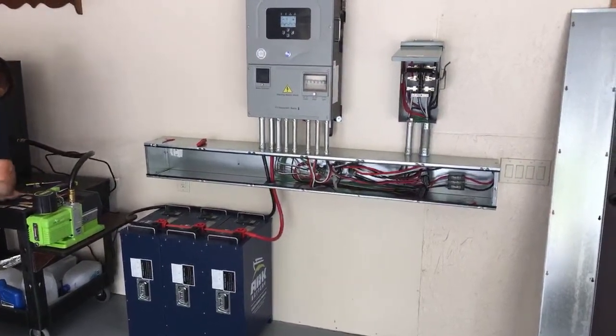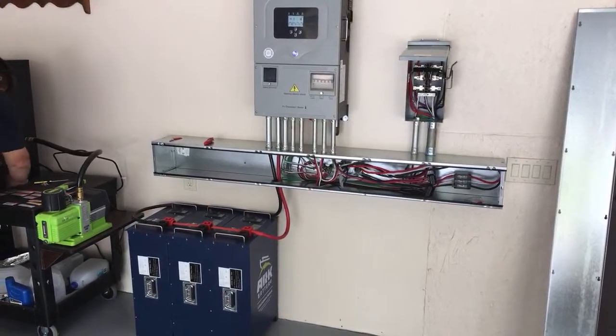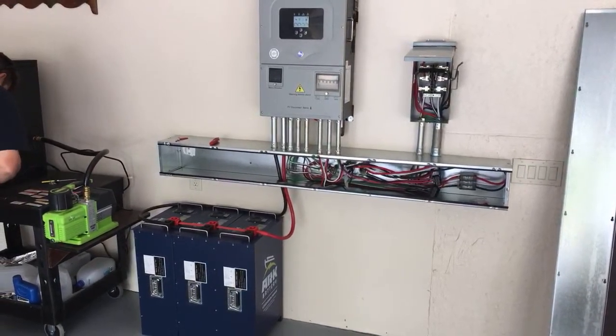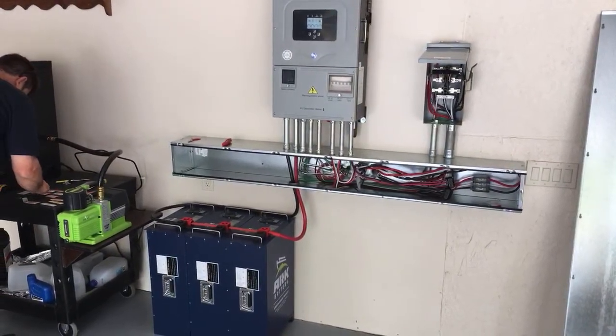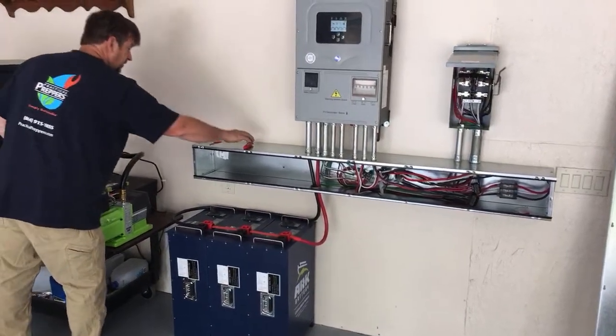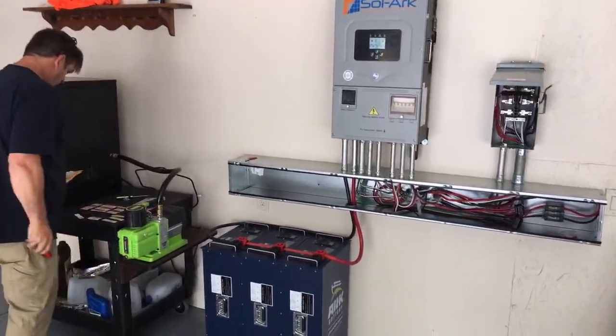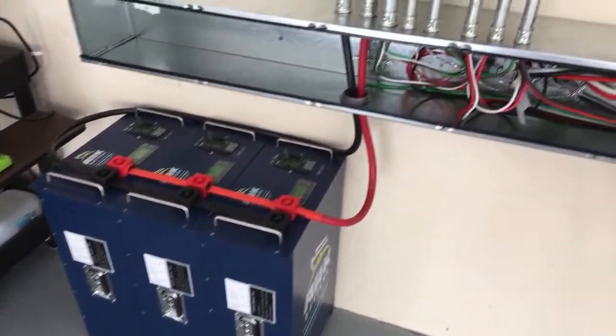We used a lot of SER cable on this job because we had to build it for 100 amps, even though the SolArk is only a 50-amp inverter on a 50-amp breaker. The SER cable is a little difficult to work with, but we've got room for another inverter.